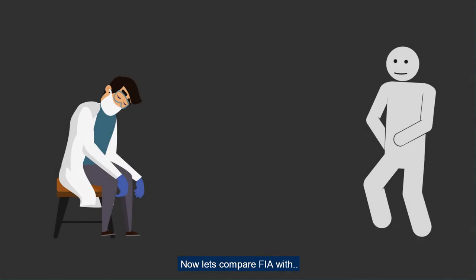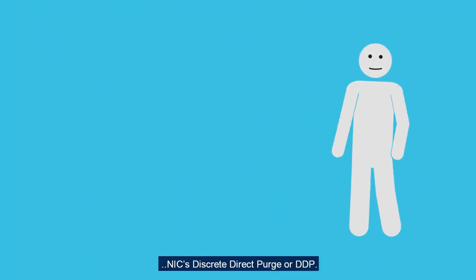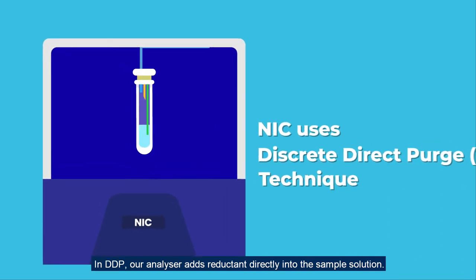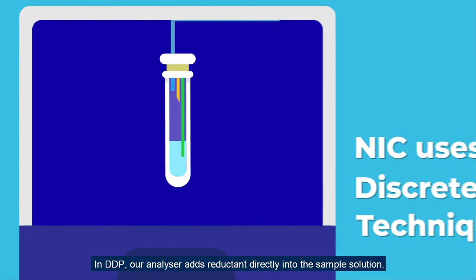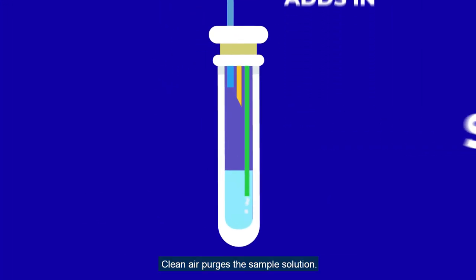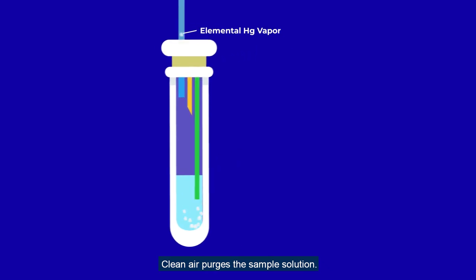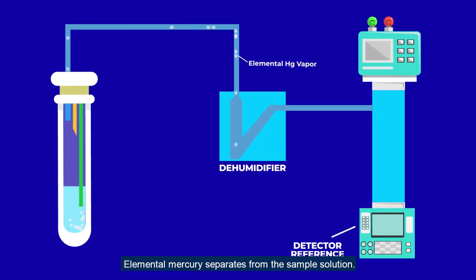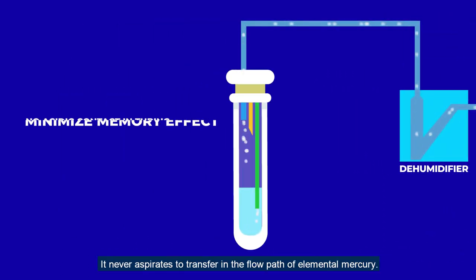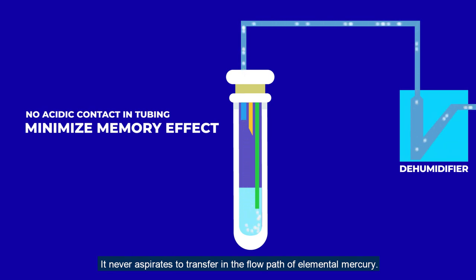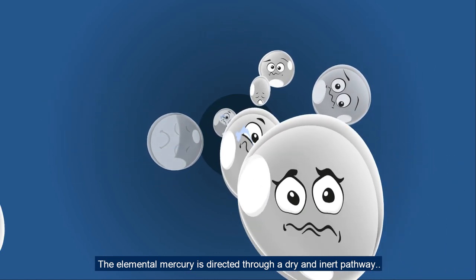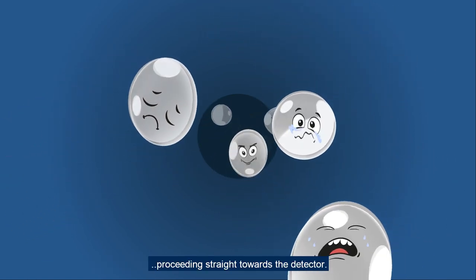Now let's compare FIA with NIC's Discrete Direct Purge, or DDP. In DDP, the analyzer adds reductant directly into the sample solution. Ionic mercury reacts and reduces to elemental mercury. Clean air purges the sample solution, and elemental mercury separates from it — the acidic portion remains behind. It never aspirates to transfer in the flow path of elemental mercury. The elemental mercury is then directed through a dry and inert pathway, proceeding straight towards the detector.